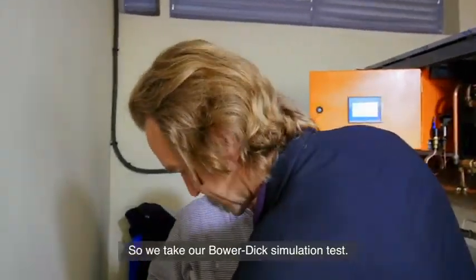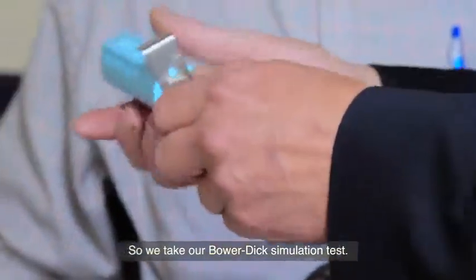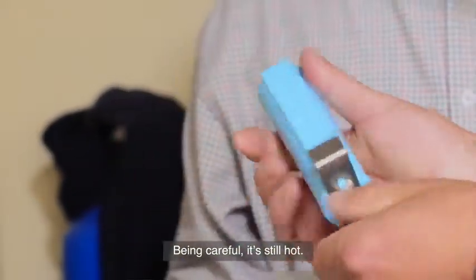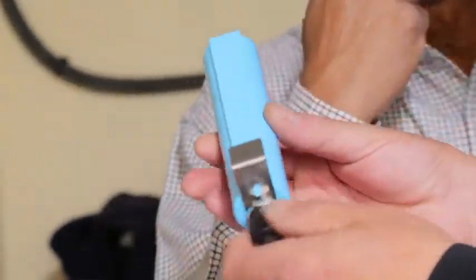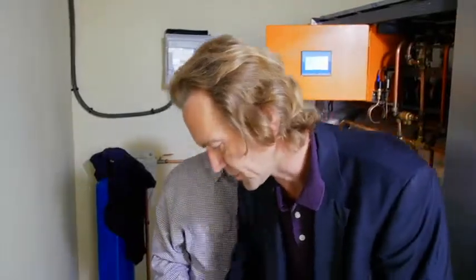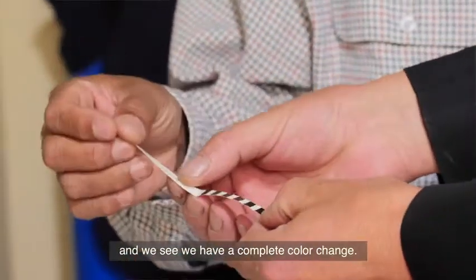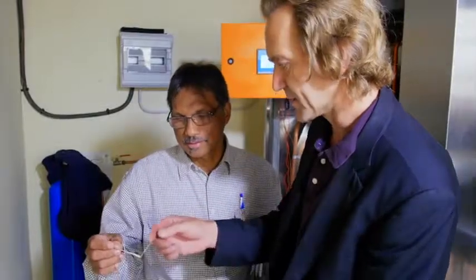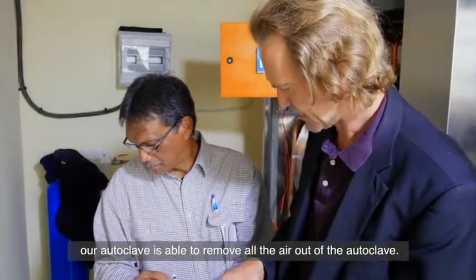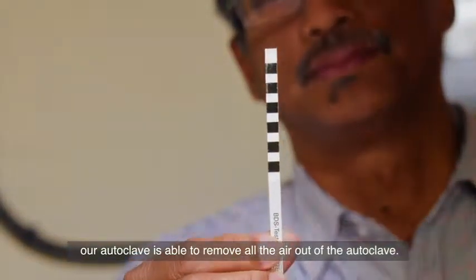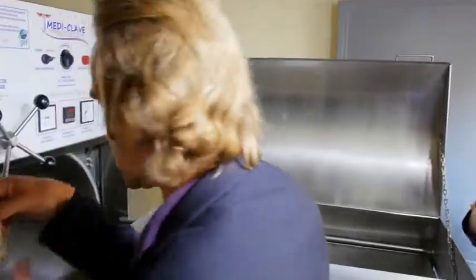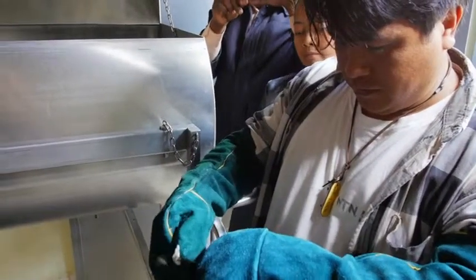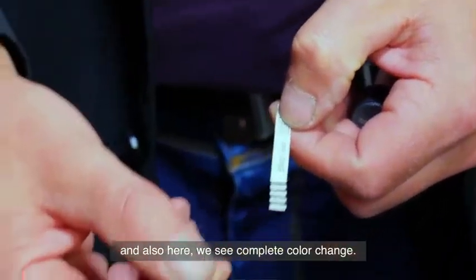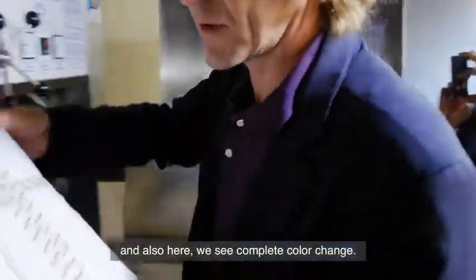Then we take our Bowie-Dick simulation test. Again, careful, it's still hot. We open it and we check the color. And we see we have a complete color change. So again, this means that our autoclave is able to remove all the air out of the autoclave. And also here we see complete color change. So we have our test pack.